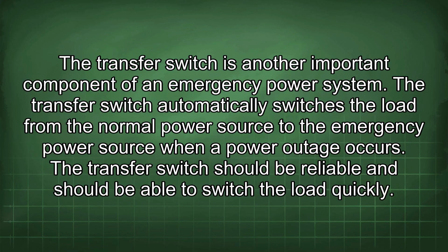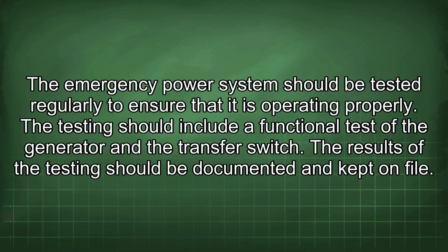The transfer switch is another important component of an emergency power system. The transfer switch automatically switches the load from the normal power source to the emergency power source when a power outage occurs. The transfer switch should be reliable and should be able to switch the load quickly. The emergency power system should be tested regularly to ensure that it is operating properly. The testing should include a functional test of the generator and the transfer switch. The results of the testing should be documented and kept on file.